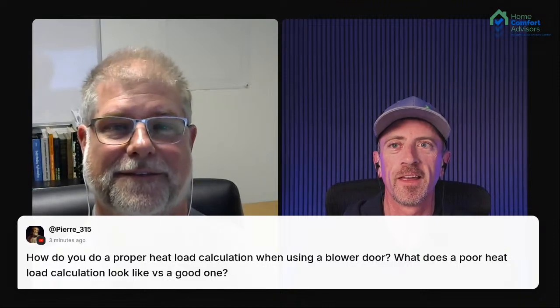If it magically comes out to 500 square foot to the ton, it's a poor load calculation. That means somebody has fudged the numbers to try to fit what they're comfortable with.